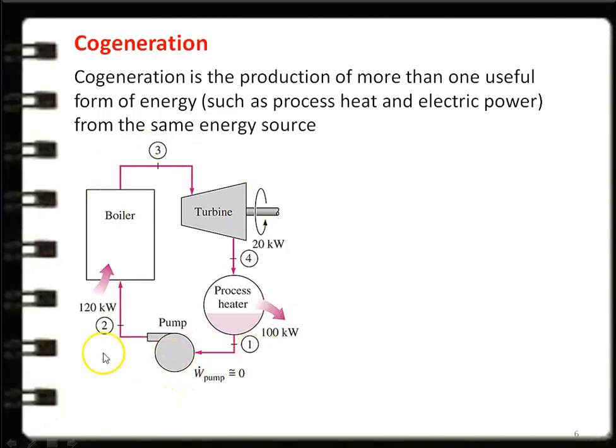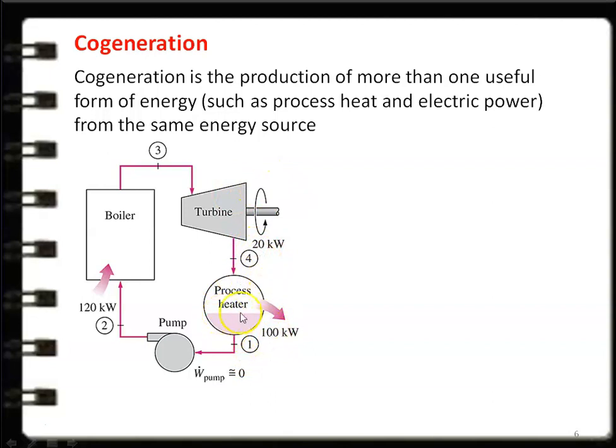For a numerical understanding: assume 120 kW of heat is given in the boiler to convert water into steam. Out of 120 kW, 20 kW is produced as mechanical power, and the remaining 100 kW is used in the process heater for industrial process heating. This is called a simple cogeneration plant.